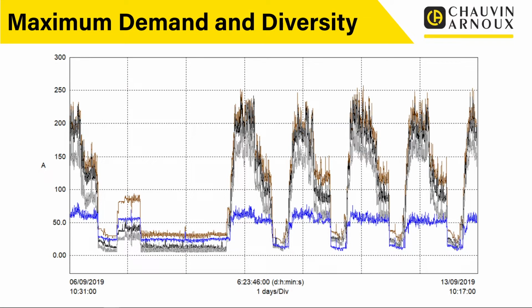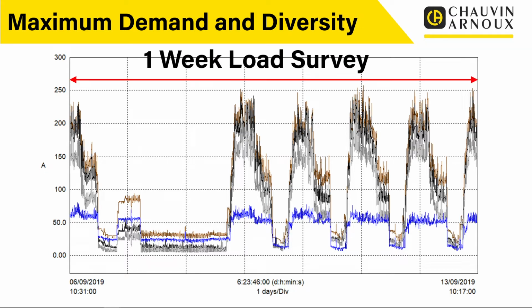So what we've got here is a load characteristic, a load graph. This is a load survey that was taken over about a one week period, and this was done using one of our PEL power and energy loggers. It's monitoring the current on 3 phases, L1, L2, L3, and a neutral. You can see the colours on there, the brown, black and grey and the blue to denote that. So this is showing you how detailed we can get.